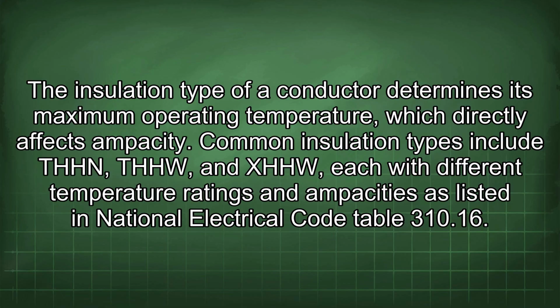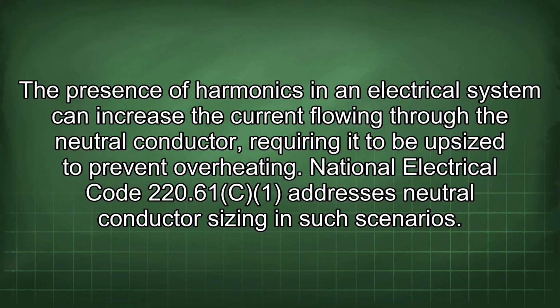Common insulation types include THHN, THHW, and XHHW, each with different temperature ratings and ampacities as listed in National Electrical Code Table 310.16. The presence of harmonics in an electrical system can increase the current flowing through the neutral conductor, requiring it to be upsized to prevent overheating. National Electrical Code 220.61 addresses neutral conductor sizing in such scenarios.